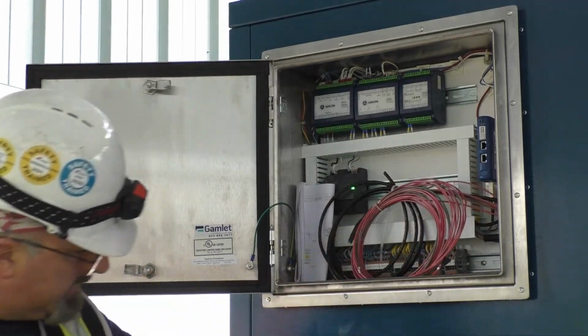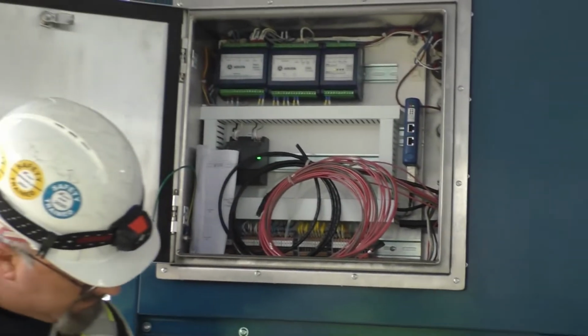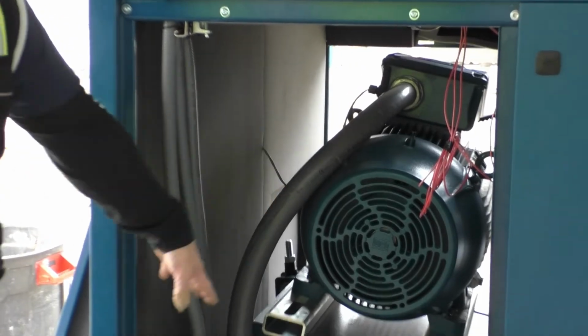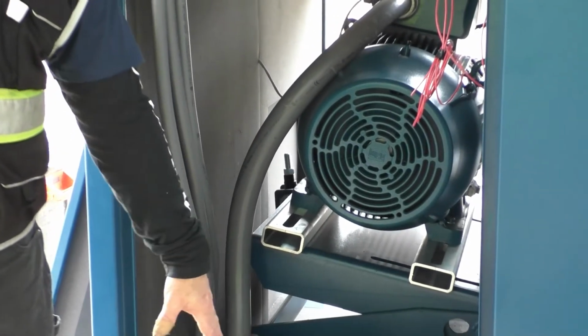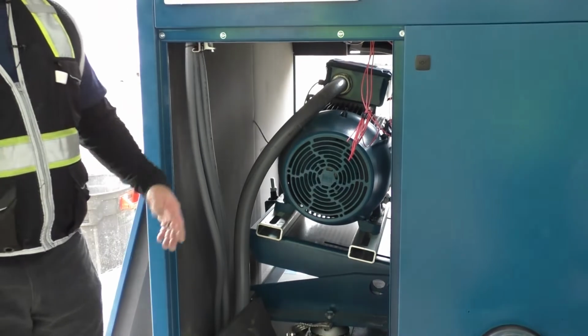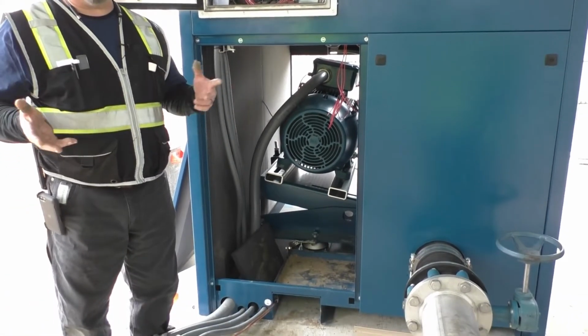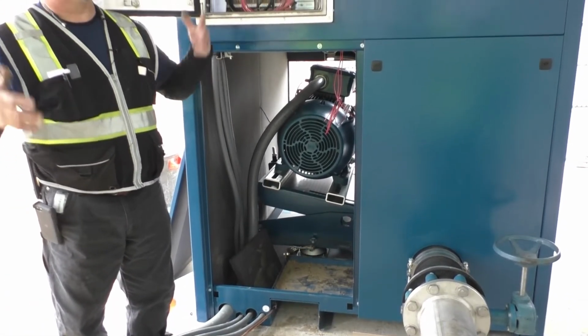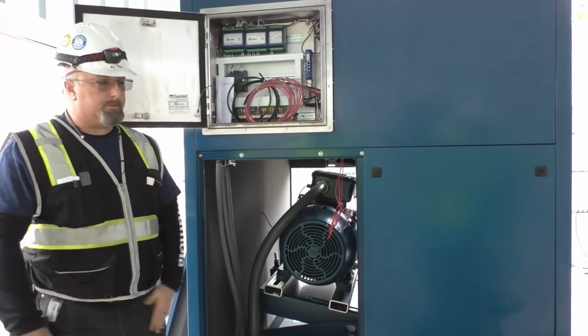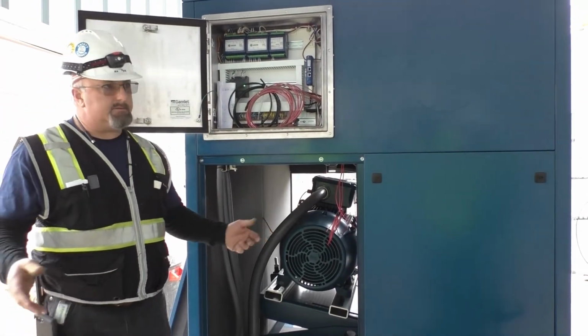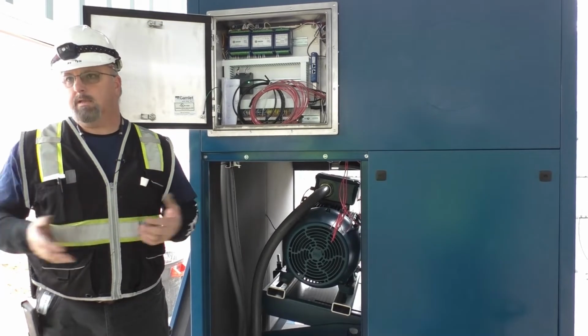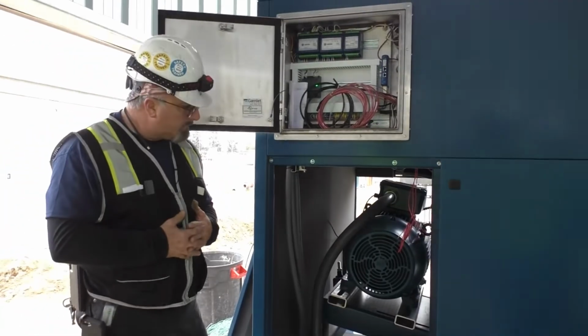Now, as you look down inside the blower compartment, you have your attached fan on the motor. You have a grounding strap from the base frame to the cabinet. You have a grounding strap from the cabinet to earth ground. That gives you your protection both ways for the motor, and in case lightning was to hit, it gives it a place to go. It's not a guarantee that it'll protect everything, but it gives you a better chance than if you didn't have it.